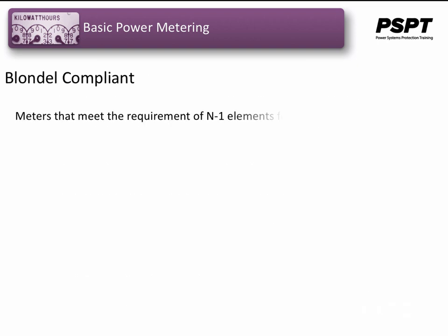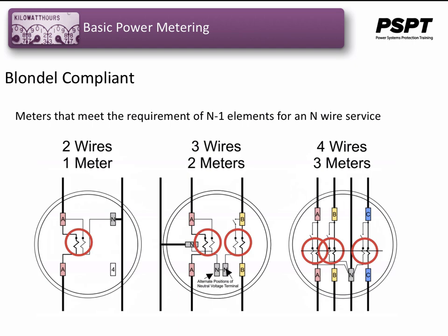If a meter is wired correctly and the right number of metering components or elements are present for metering a system of n wires, then meters that meet the requirement of n-1 elements for n-wire service are said to be Blondel compliant. And it's usually accepted that there are no errors in this type of metering system that are incurred by the connections. There may be errors due to the PTs or the CTs themselves, but as far as the connections are concerned, it should be reading 100% accurate.